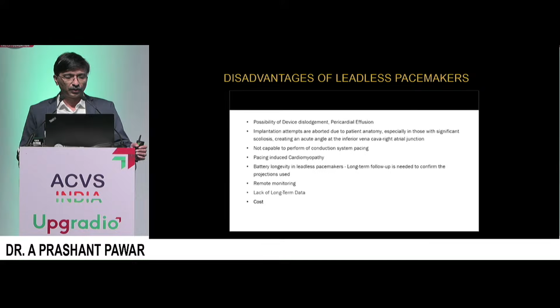We can't do conduction system pacing with these leadless pacemakers, because these leadless pacemakers have to be in this trabeculated part. It has to be in the lower septum. We can't go to the higher septum. The pacing induced cardiomyopathy remains the same. Battery longevity in a leadless pacemaker roughly lasts around 12 to 13 years, but not even a decade has completed for the leadless pacemaker, so we don't know the long-term data yet. Remote monitoring is not possible with leadless pacemaker, and long-term data is not there. Cost is a major concern in our country, where 10.5 to 11 lakhs is a huge amount.